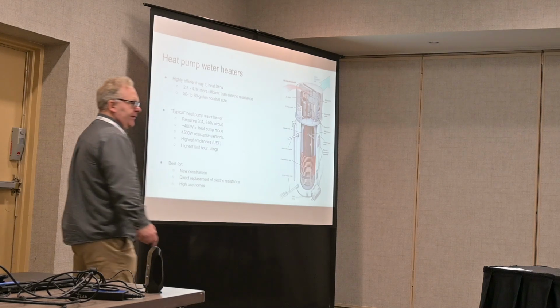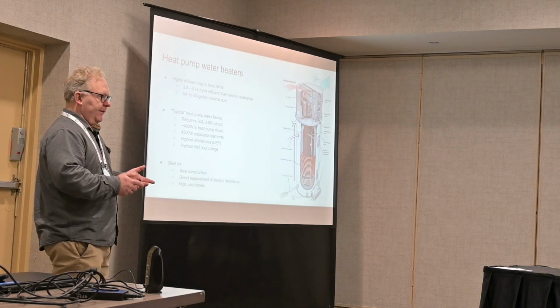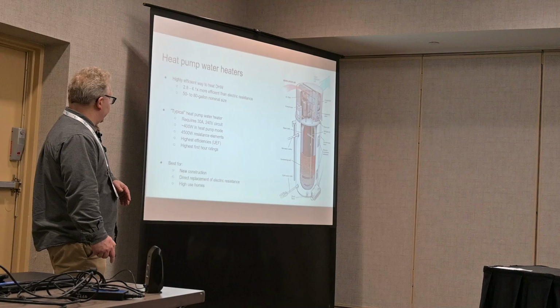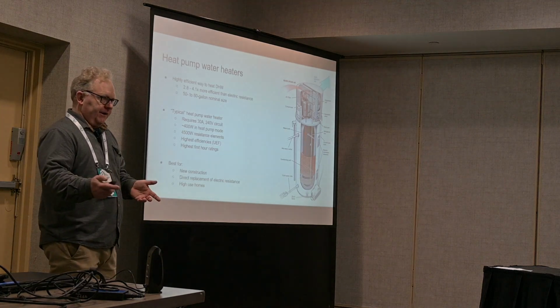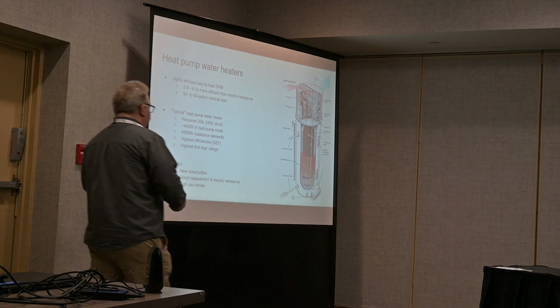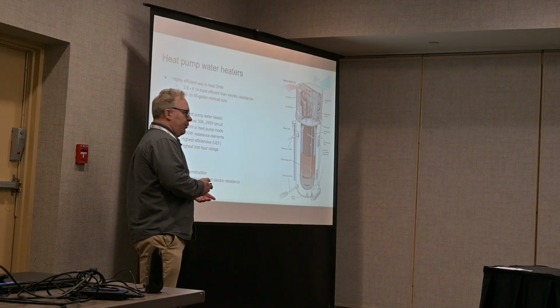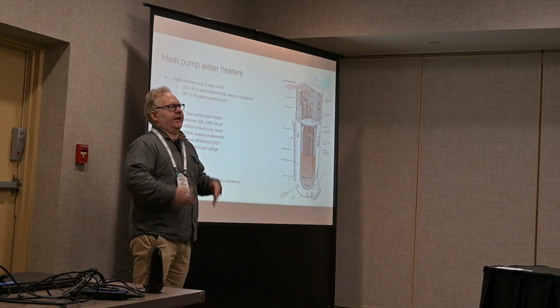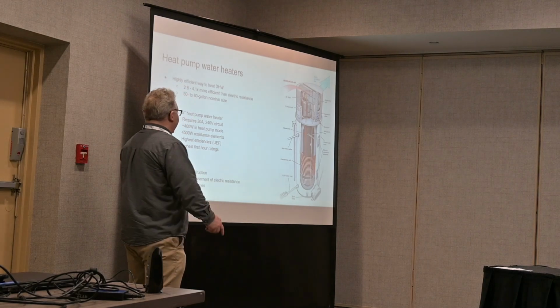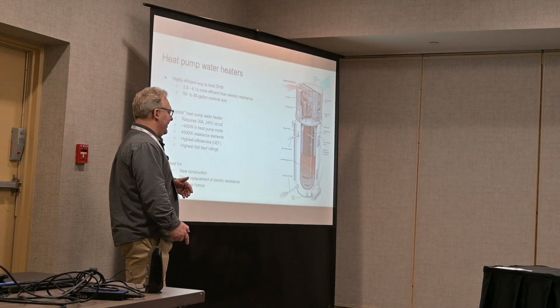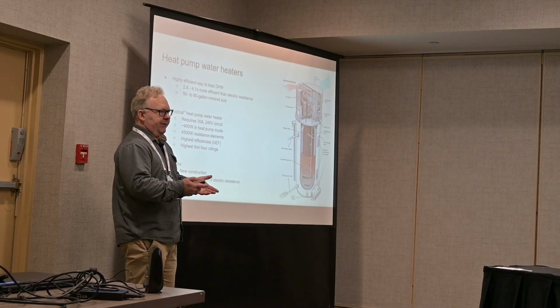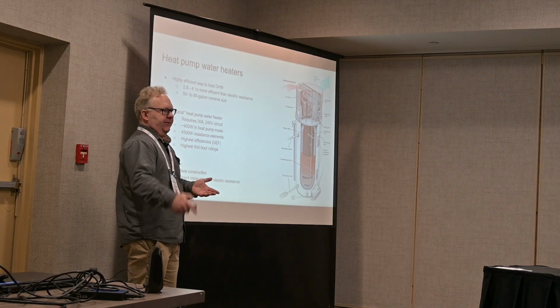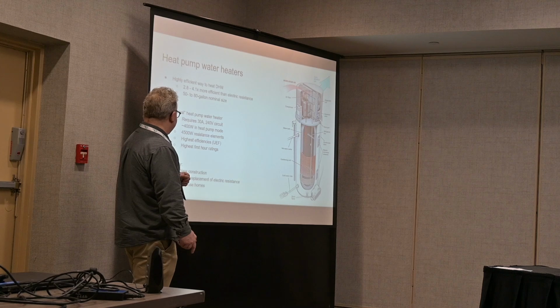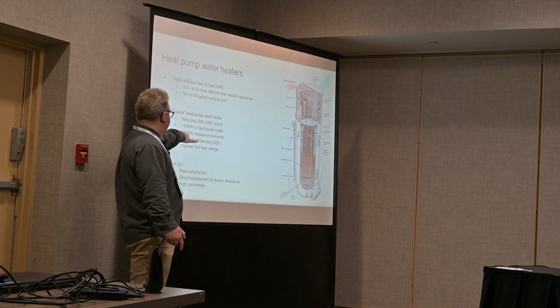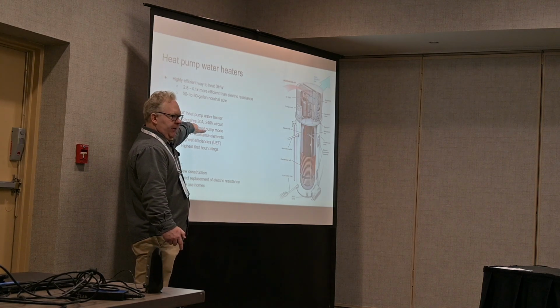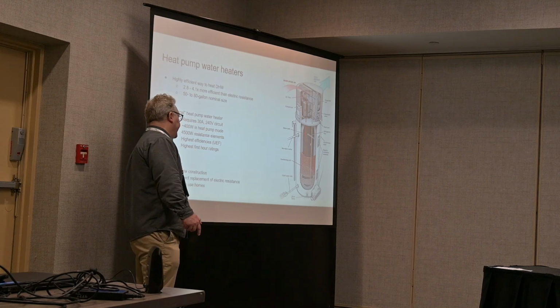Okay, now heat pump water heaters. These are the other big thing that we're electrifying through home performance. These are highly efficient. So, a heat pump water heater installed in heat pump mode, not like I had it, is going to heat your water with 3+ times the efficiency of a standard electric resistance tank. And when it's running in heat pump mode, it might only draw 400 or 500 watts.